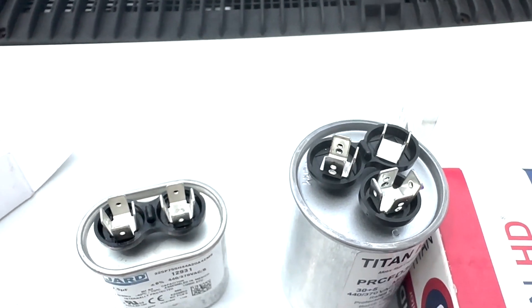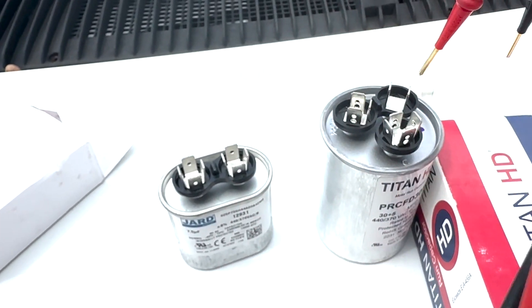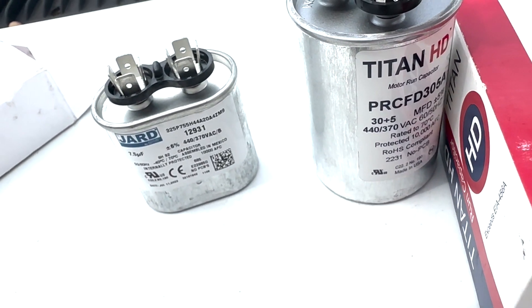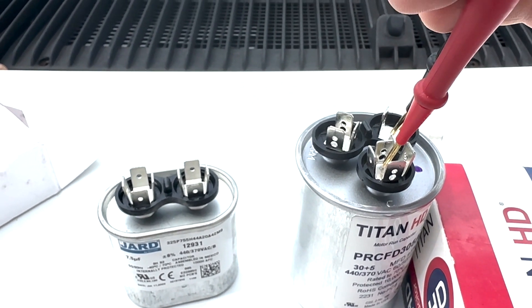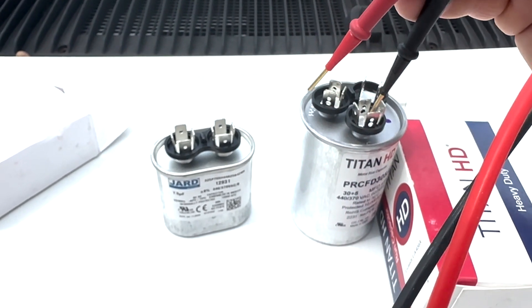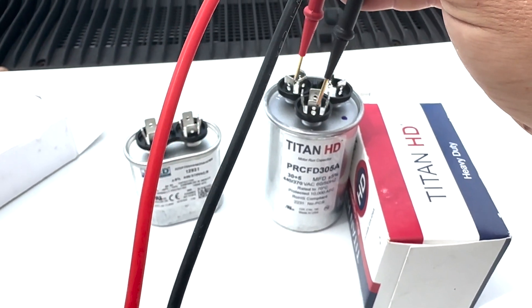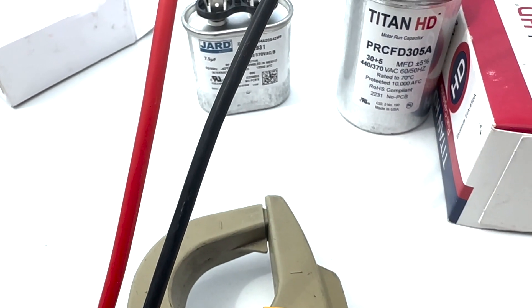Here's the dual run capacitor — this one has one common, a hermetic over here which is for the compressor, and then the fan over here. So it's 30 plus 5: 5 microfarads on the fan side, 30 on the compressor side. If we touch from common to fan, we get 5 microfarads — this is brand new so it should be good, but this is just how you check it. And then if you check from common to hermetic, we get 30.5 — which, again, is within that 5% tolerance. That's how we would know that the capacitor is good.